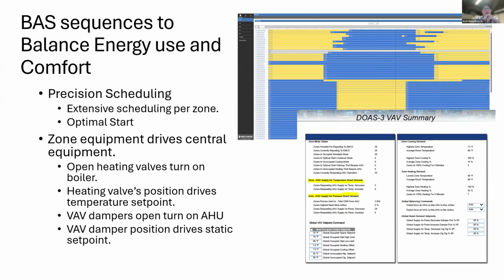Some of the sequences that we use to balance energy and comfort, of course, is scheduling. We schedule every zone. Every classroom has an individual schedule. We don't schedule a building. We don't schedule a floor. We schedule every classroom. Every classroom has an optimal start attached to it. So the zone can be up to operating temperature by the time the teacher and students arrive. And Robert touched on this too. I'll go into more detail.